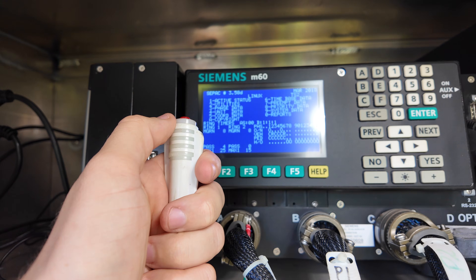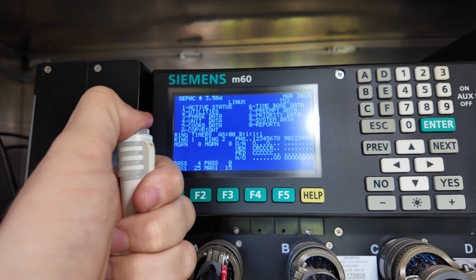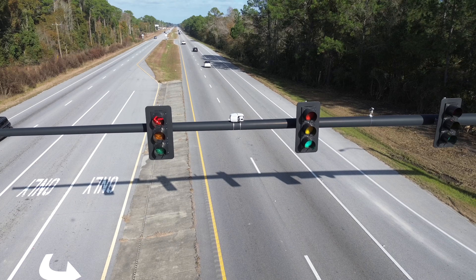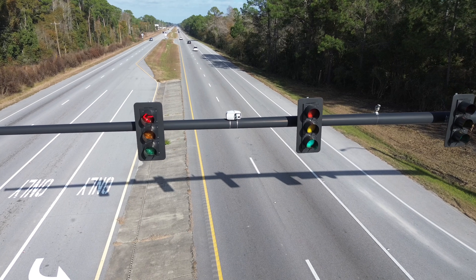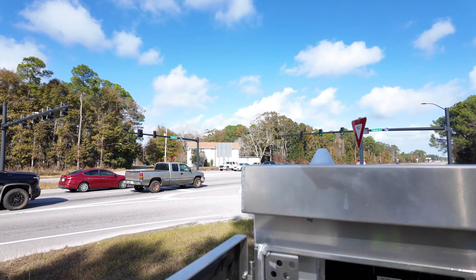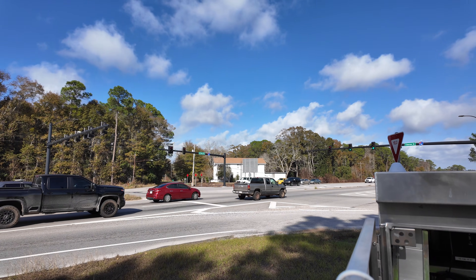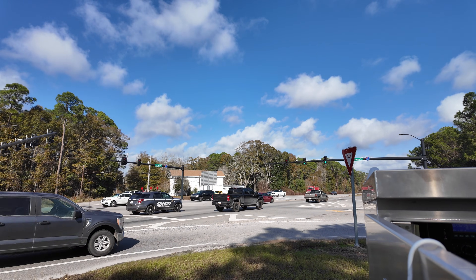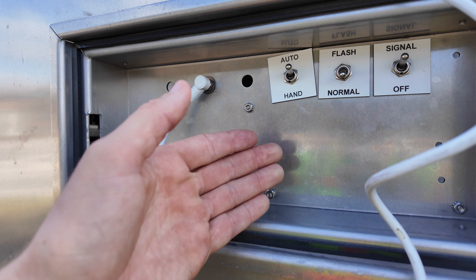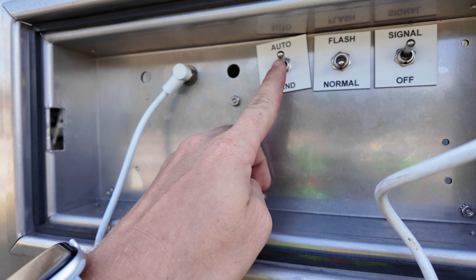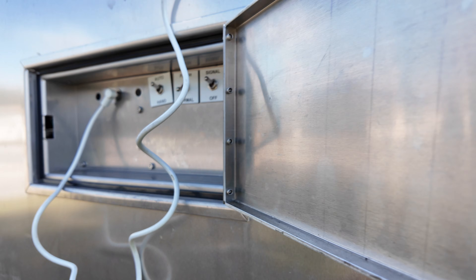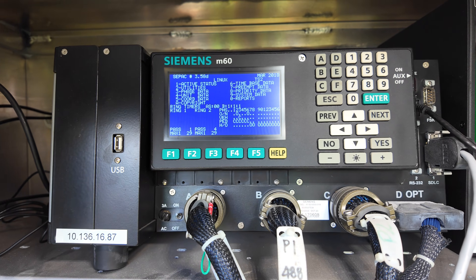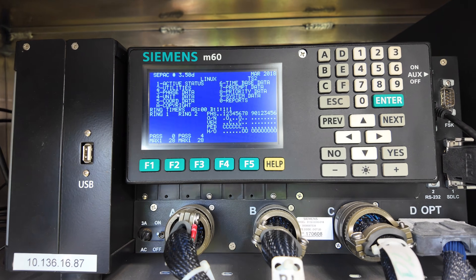Once the left turn lanes have cleared out, pressing the button again immediately starts the cycle and allows phases two and six — Highway 90, the busier highway — giving them a green light. Once you no longer need the button, you simply flip the switch back to auto, and the controller automatically takes control of the intersection again.